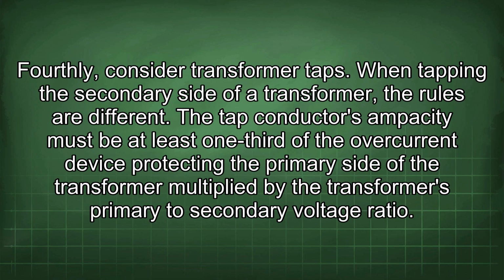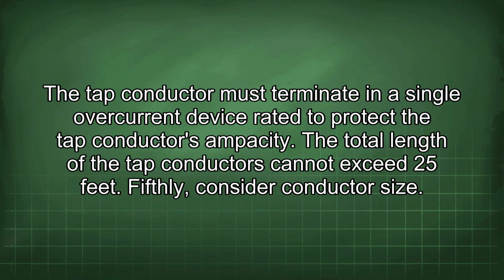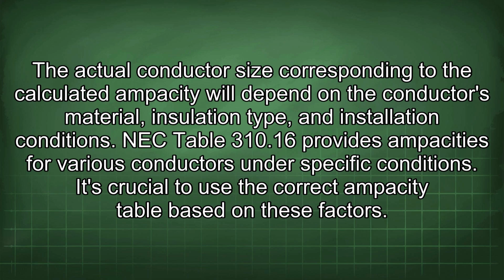Fourthly, consider transformer taps. When tapping the secondary side of a transformer, the rules are different. The tap conductor's ampacity must be at least 1/3 of the overcurrent device protecting the primary side of the transformer multiplied by the transformer's primary to secondary voltage ratio. The tap conductor must terminate in a single overcurrent device rated to protect the tap conductor's ampacity. The total length of the tap conductors cannot exceed 25 feet. Fifthly, consider conductor size. The actual conductor size corresponding to the calculated ampacity will depend on the conductor's material, insulation type, and installation conditions. NEC Table 310.16 provides ampacities for various conductors under specific conditions.